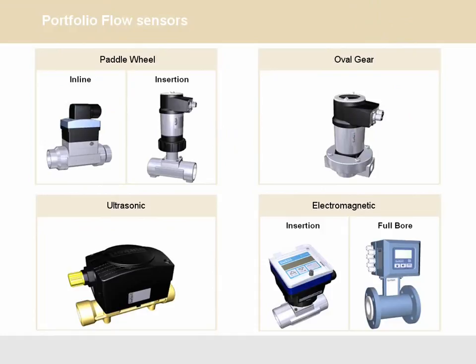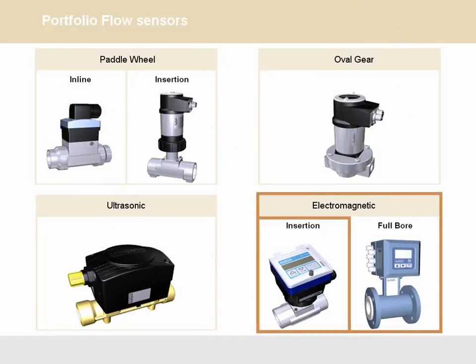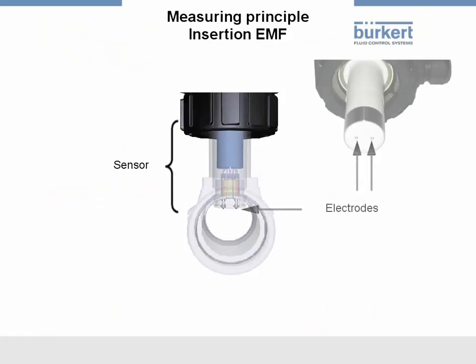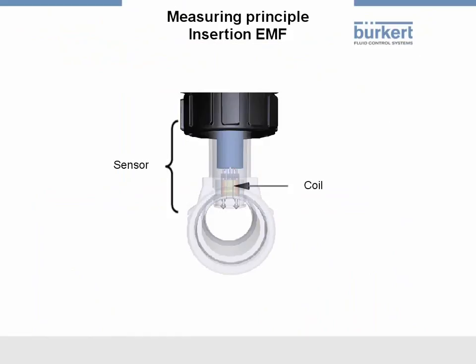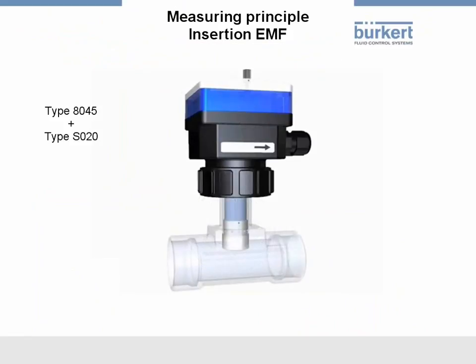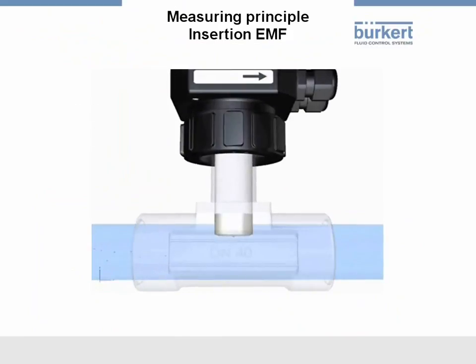Now let's examine the insertion EMF principle more closely. Two electrodes are inserted on the end of the sensor that are in contact with a conductive medium, and an electric coil above the electrodes. The coils generate an alternating magnetic field. As soon as the conductive medium flows through the magnetic field, a current is induced in the medium, which changes proportionally to the flow speed. This means the higher the flow speed, the higher is the induced current, and therefore the voltage measured at the electrodes. The electronic circuit converts the voltage signal to standard signals, either to pulses or a 4 to 20 milliampere DC current.